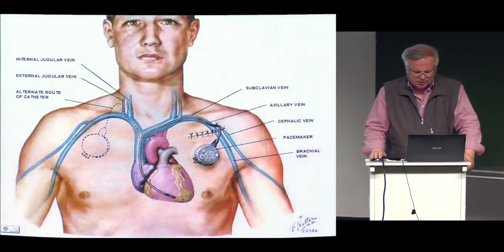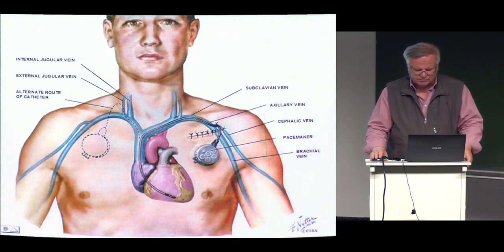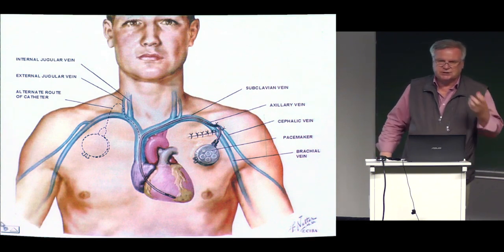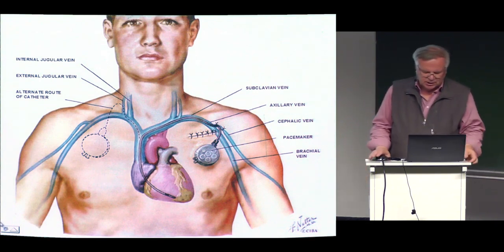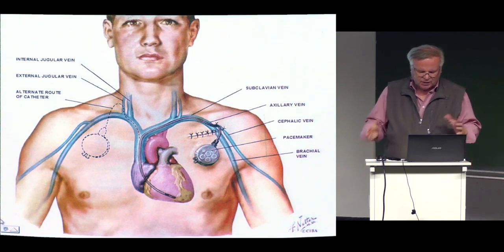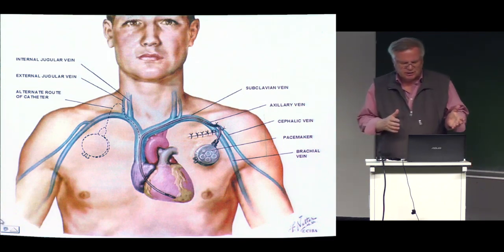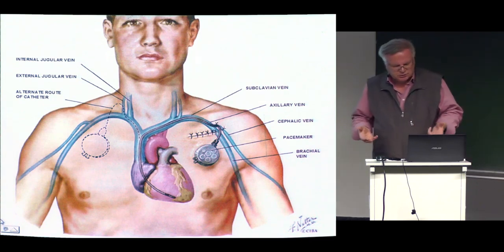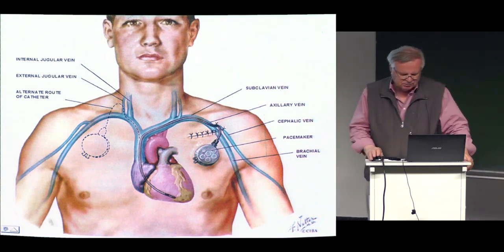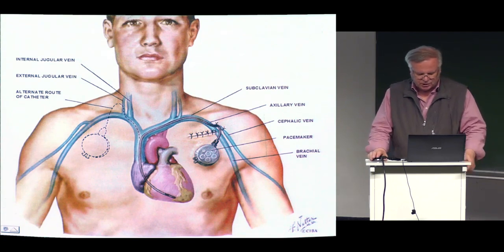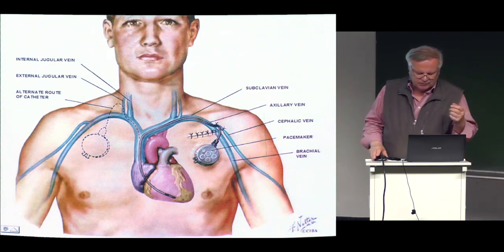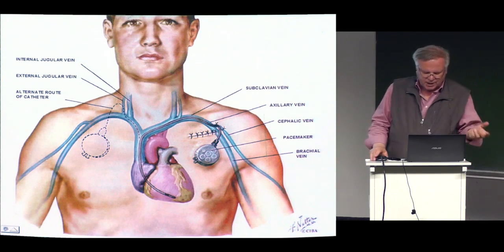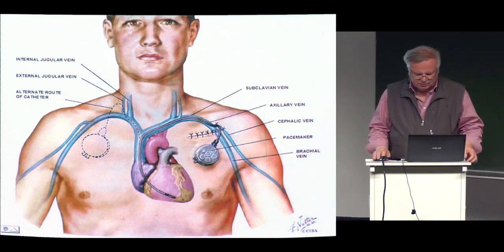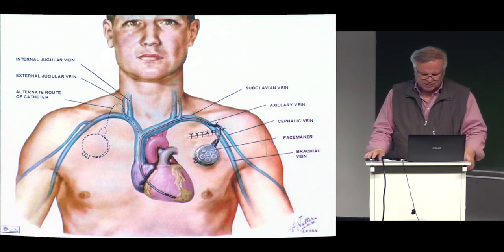The most simple pacemaker, the original first pacemakers, were just impulse generators giving a fixed rate impulse. Even if the heart returns to normal state, it still gives impulses all the time, which is not needed. This causes problems with the heart's operation when the ventricles get stimulus from the atria and from the pacemaker as well. So that kind of fixed rate pacemaker is not necessarily good.